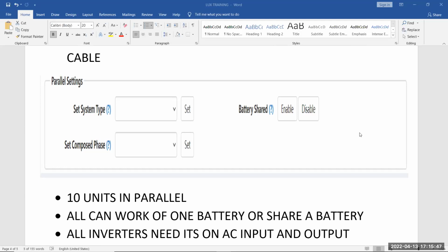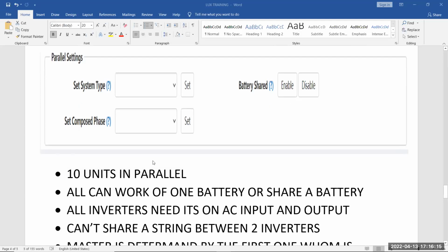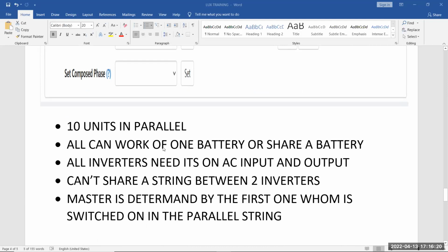Now on batteries shared, if it's a battery that's communicating, only my master inverter is necessary for a communication cable between the battery pack and the inverter. My master inverter will relay all the information to the rest of the inverters. And if your communication between your inverters is correct, all my inverters will display the battery percentage and the power and all of that information. So that's basically that for parallel settings. I'll show you on the screens as well, a few of the settings that we can do there.